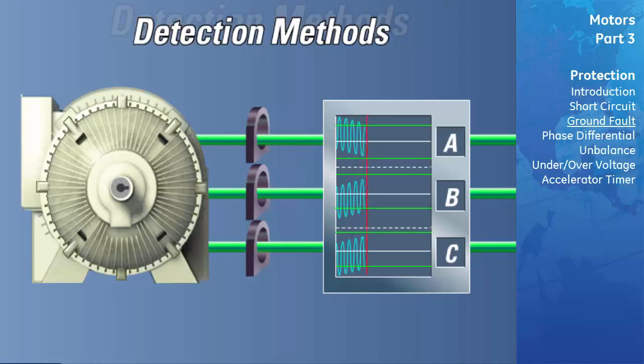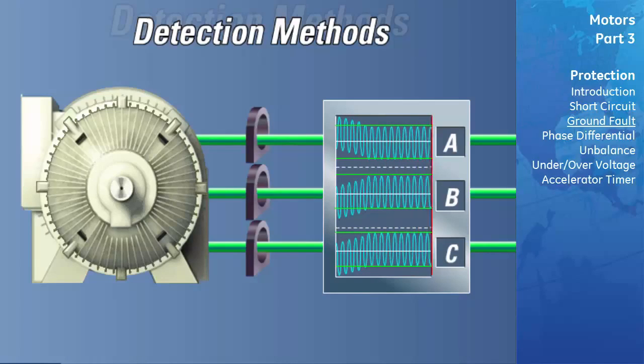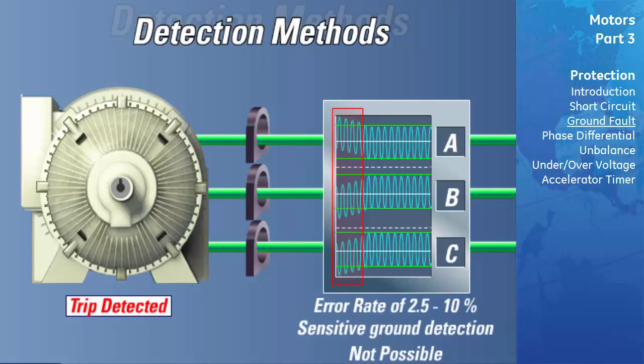During motor start, the motor's phase currents typically rise to magnitudes in excess of six times the motor's full-load current. The slight mismatch of the differential CTs, combined with the relatively large phase current magnitudes, produce a false differential current which will be seen by the relay. This current will be misinterpreted by the relay as a ground fault unless the ground fault element's pickup is set high enough to disregard this error.